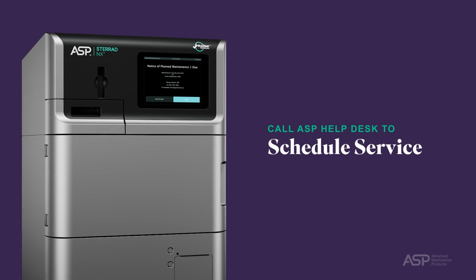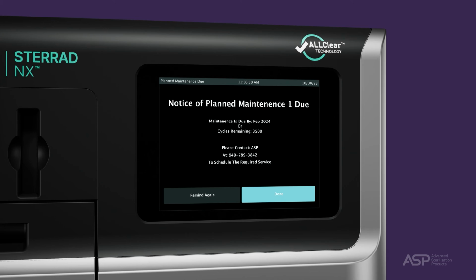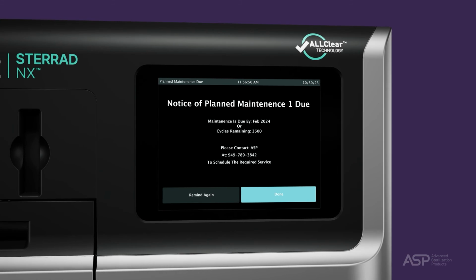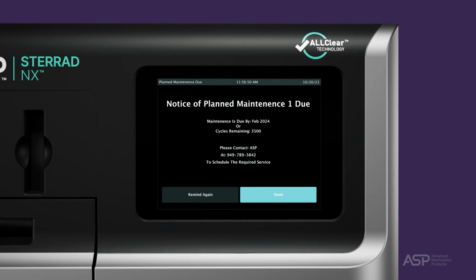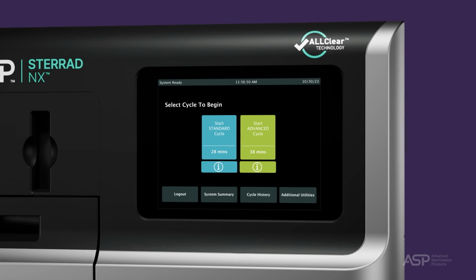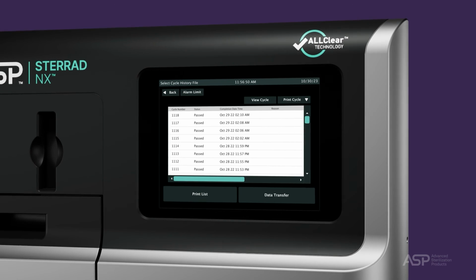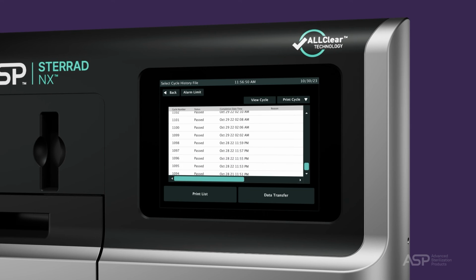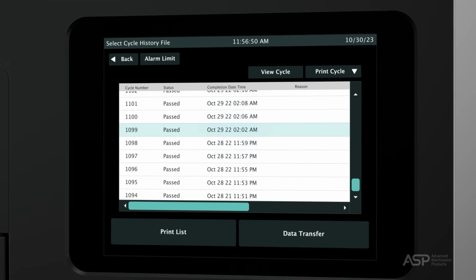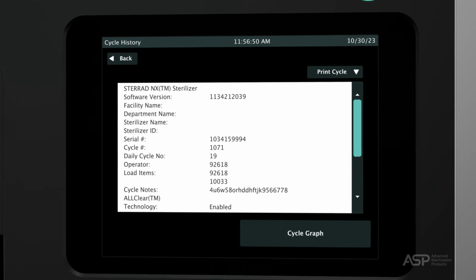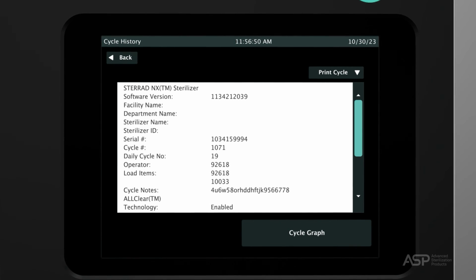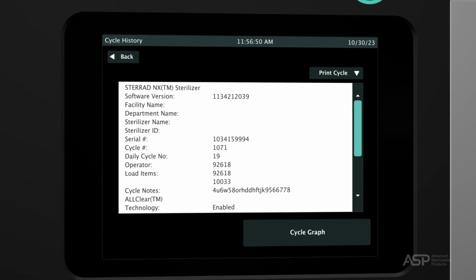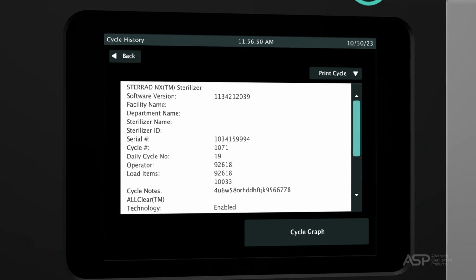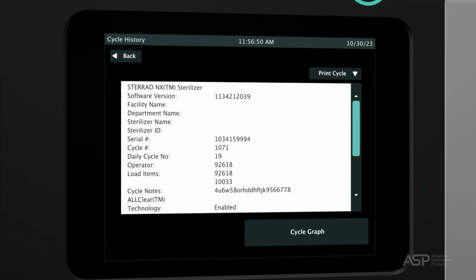When the message is received to schedule maintenance, the system contains information for the service engineer regarding the type of planned maintenance to be performed. Let's look at what's on the utility screen. Cycle history files contain very detailed information about each sterilization cycle. The files include identifying information about the operator, load, time, date, cycle duration information, stage-by-stage data from the sensors and controls, and related technical items.